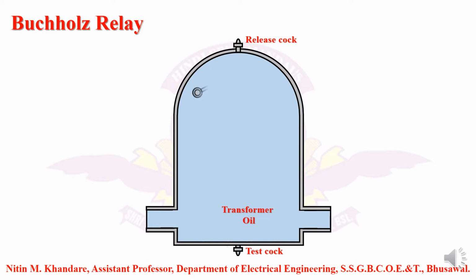Next component is nothing but the float, and along with the float we are connecting one mercury switch. Mercury switch is a simple form of the switch which is having the mercury level inside the tube as well as having the two terminals. Then the two terminals of the mercury switch are connected with an alarm system. If the incipient faults are there, then an alarm rings there which identifies the incipient fault which may occur inside the transformer.